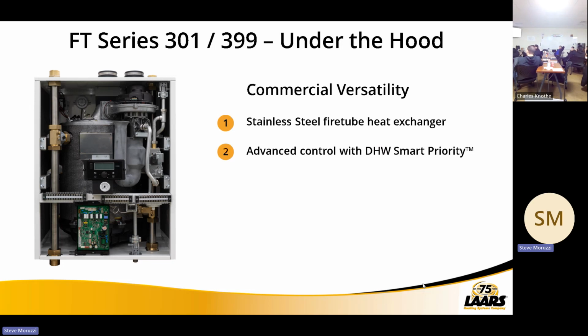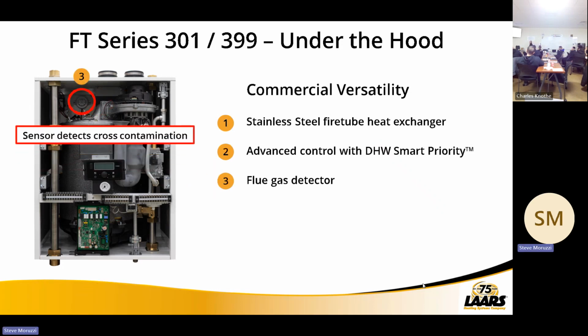So by the way, when you're doing a combustion analysis, you want to consider this. Why? If I go 45 feet of combustion air and 3 elbows, that's a restriction. It's like sucking through a straw. You need to take that into consideration, any negative cabinet. All right, but so if cross-contamination exists, we're coming into a negative cabinet, we can identify that. So we have a sensor right here in the cabinet, right next to where the fresh air comes into that cabinet, right? On the other products, we would have to put some type of sensor in the ducting to that blower. Okay.